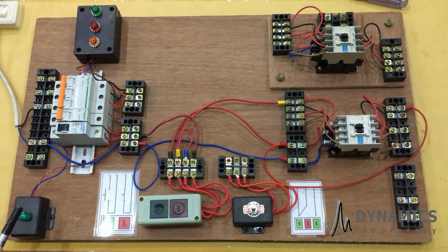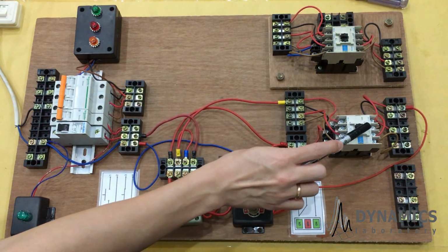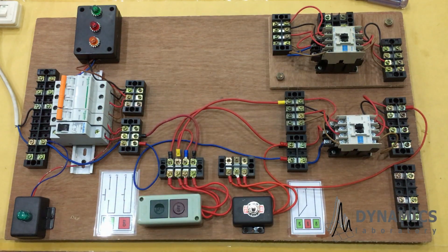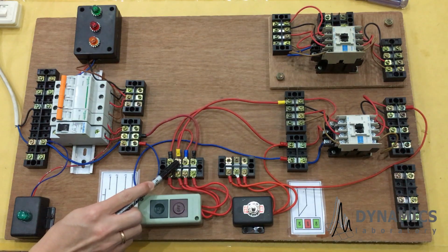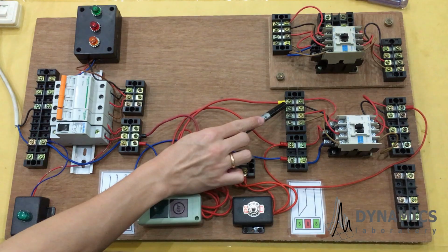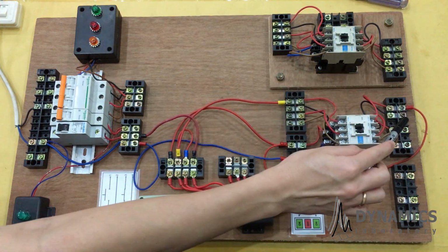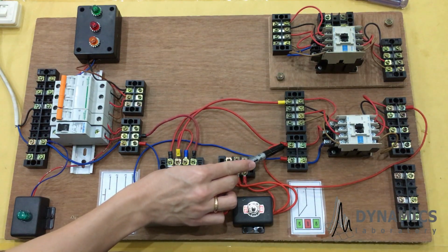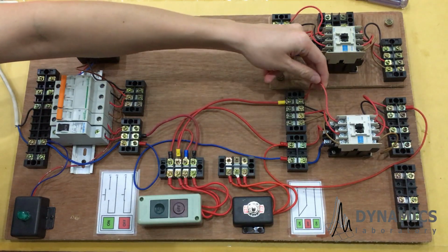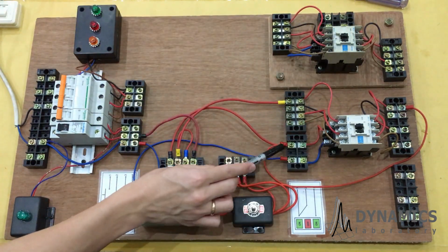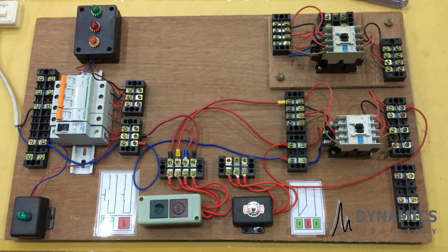To complete the latching circuit, we have to utilize terminal 13 and also 14 on the contactor. Remember, at the beginning of the video, I have already introduced you to terminal 13 and 14 for low control circuit, or low current circuit. Therefore, leg number 2 of the push button connects to terminal 13, and terminal 14 is connected back to the coil contactor. You can see this one is terminal 13 and on the other hand is terminal 14, connected back to the coil contactor. Let's try it.